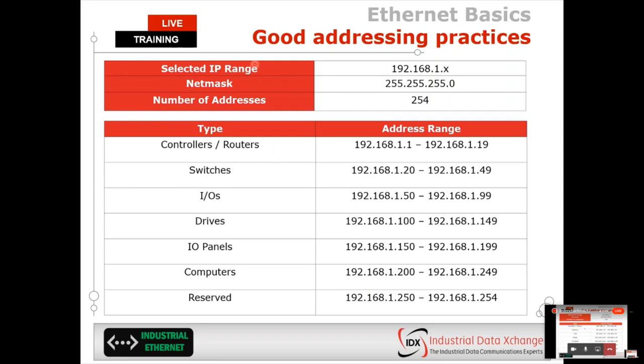In this application, I'm using the 192.168.1 range. So here's my net ID, 192.168.1. Any device with the same net ID can communicate on this network infrastructure. My net ID is the first three parts as defined by the 255s in my subnet. In the first 20 addresses, I assign all my controllers. The second 20 addresses go to all my switches to distribute my I/O. My I/O stations for digital inputs or distributed I/O, I assign in the 50 up to 99 range.